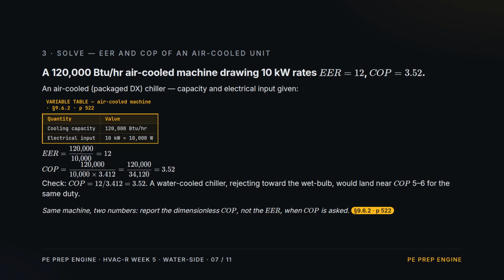Solve. An air-cooled packaged machine. Capacity is 120,000 BTU per hour, and it draws 10 kilowatts, which is 10,000 watts. Capacity over the raw watts gives an EER of 12. Divide instead by watts times 3.412, and COP is 3.52. And 12 over that same factor checks to 3.52 as well. A water-cooled chiller on the same duty, rejecting toward the wet bulb, would land near a COP of 5 to 6.